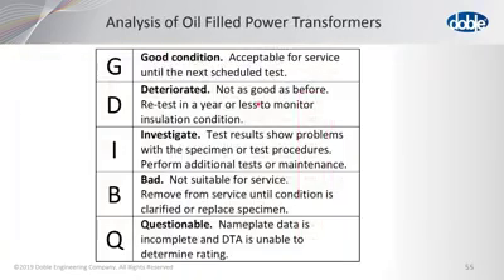Now, what does that G rating mean? Well, it's good condition, acceptable for service until the next scheduled test. So in other words, you can now do a routine test in 5 years, 6 years, whatever your recommendation is. Deteriorated: not as good as before, and retest in a year or less to monitor the insulation condition. You know, what is the trend? Is it getting higher, or is it just staying where tested previously? Investigate: test results show a problem, you should investigate. Bad: not suitable for service.